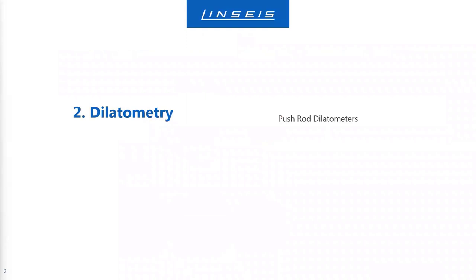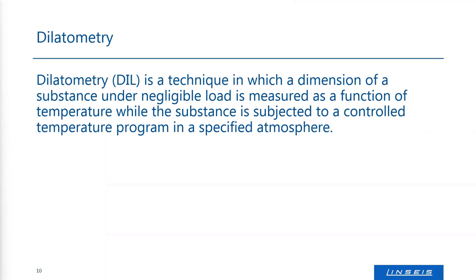A big field where hydrogen is applied is our dilatometers. We have more or less two kinds of dilatometers: pushrod dilatometers and optical dilatometers. The pushrod dilatometers are standardized — there are ASTM norms and European norms describing the technique. It is essentially a technique in which the dimension of a substance is measured under a small load as a function of temperature or time in a specified atmosphere.